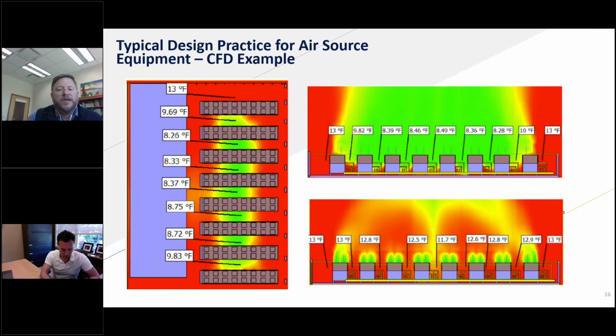Okay. And so again, as we look at a building and we look at putting this on a roof, if I have 6 inches of clearance, well, that's some airflow, but if I have 2 feet of clearance, well, then that's more airflow. And if I have 4 feet of clearance, that's even more. So that can help drive decisions on how we actually want to build up our system on the roof if we're going to be doing all air source heat pumps.